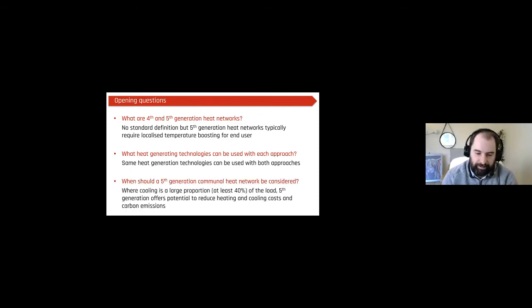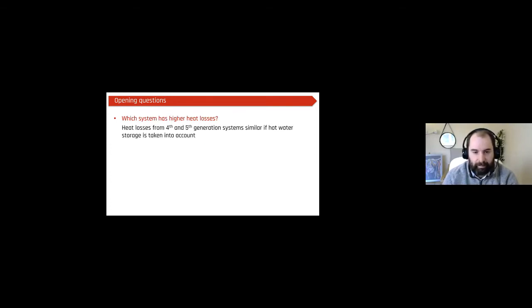And when should a fifth generation communal heat network be considered? So typically it's around about 40 to 50% of the total load should be cooling for it to be cost competitive. Which system has the higher heat losses? So if you take into account the network losses and losses within the dwellings, then they typically have similar heat losses. And finally, which approach is better?